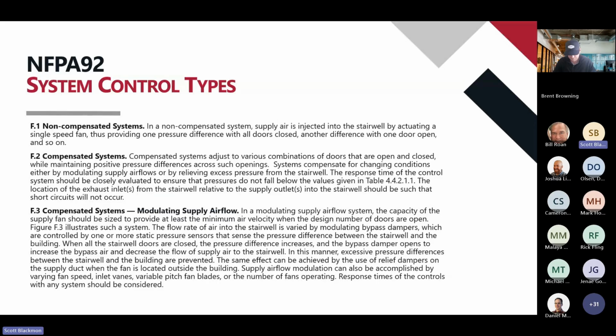Control types. So there are 3 types of control systems out there, according to NFPA. There's a non-compensated system. That's basically where you've got a fan, it's put at a set speed, and it's just a blow and go, basically. It comes on when the event occurs, blows air into the stairwell, and basically relies on doors opening and closing to relieve any kind of pressure or pressure changes.